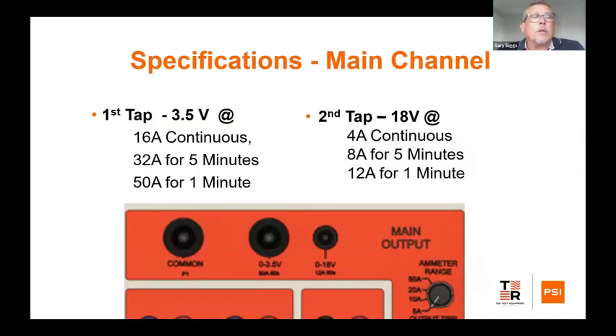The main channel from the unit has a first tap, which is a 3.5 volt tap. It'll give you 16 amps continuous, 32 amps for 5 minutes and 50 amps for 1 minute. The second tap, so effectively what you've got is a multi-tapped transformer to give you your output, is an 18 volt tap, and that will give you 4 amps, 8 amps or 12 amps.